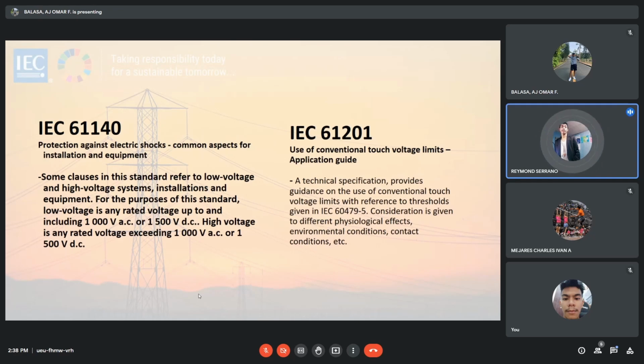So it should be noted that for an efficient design and selection of protective measures, the types of voltage that may occur and their waveform need to be considered, that is AC or DC voltage, sinusoidal, transient, phase controlled, superimposed DC, as well as a possible mixture of DC and AC forms. The installation or the equipment may influence the waveform of the voltage.